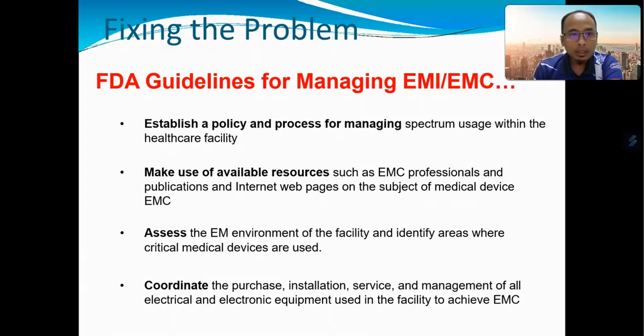All right. The next FDA guideline is about coordinating the purchase, installation, service and management of all electrical and electronic equipment used in the facility to achieve EMC. So in this process, we need to involve EMC or biomedical experts throughout the device life cycle, and not just during the purchase.